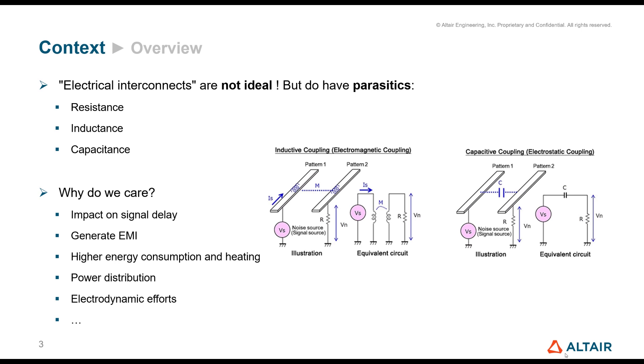The idea is that we need a solver to compute quickly parasitic behavior like resistive, inductive, and capacitive effects in busbars and other conductors. We need a solution because these devices can have large parasitic behavior, like having an impact on signal delay, generating EMI, having extra AC losses, but also having extra forces due to short circuits, for example.